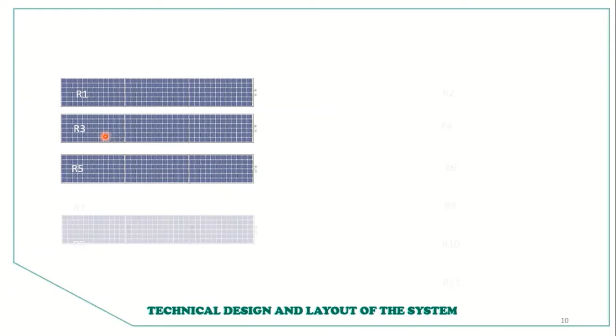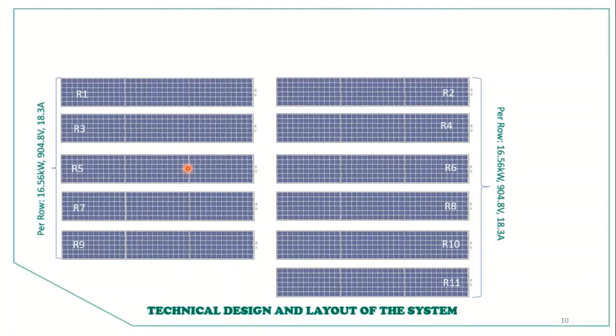Now let's look at the technical design and layout of the PV system. We have 11 rows, each consisting of two parallel strings of PV modules. Each row can produce 16.56 kilowatt of power at 905 volt, so 11 rows produce roughly 180 kilowatt.